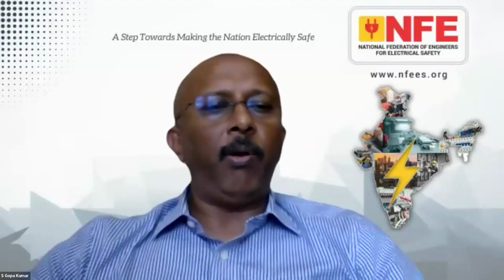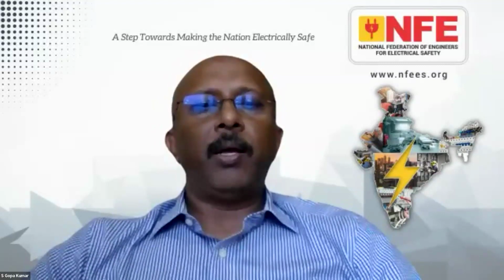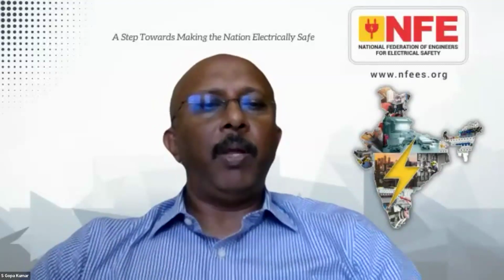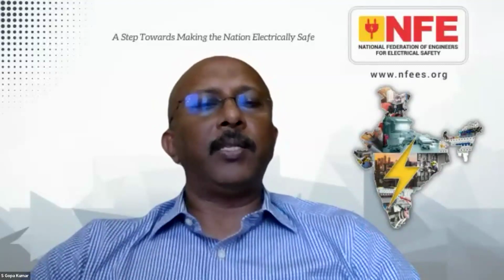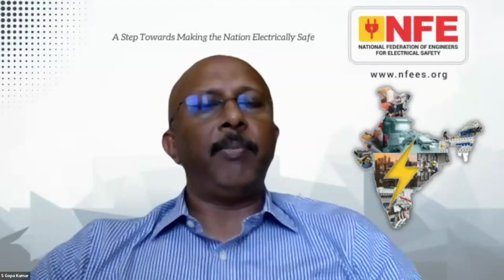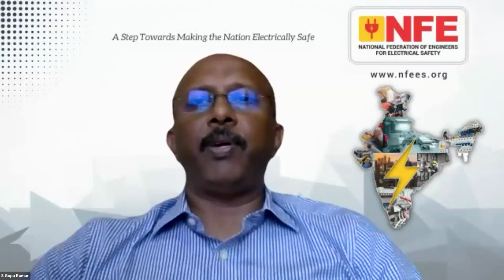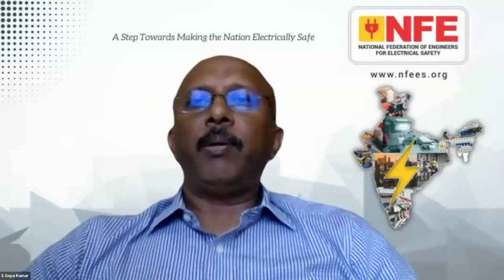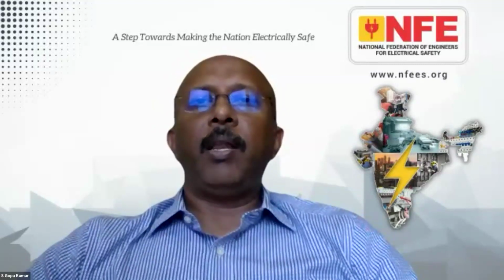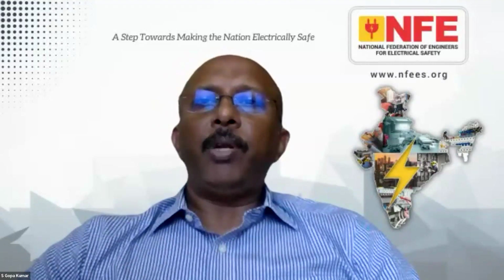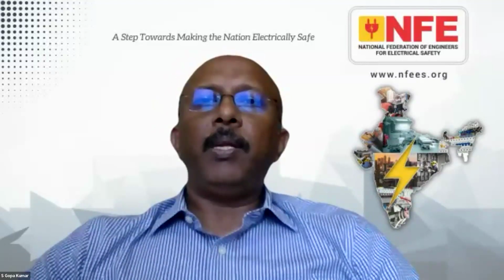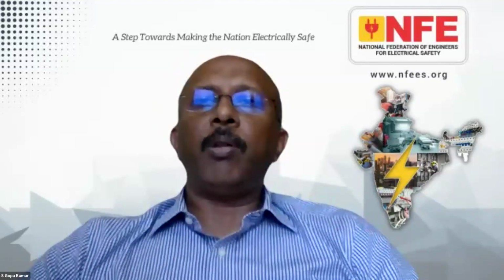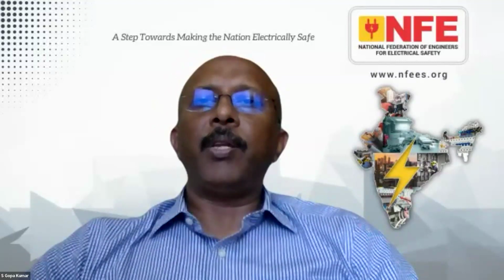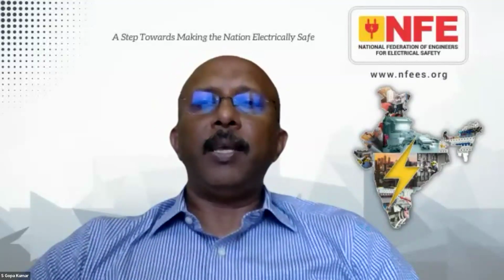If you are doing only fault loop impedance, the conclusion is probably that the efficiency of automatic disconnection is good. That's all. It doesn't mean that the installation is safe. So now, coming back to the question of Mr. Amritlal: when you are trying to test an installation, what will be the test voltage of the instrument, or the safety of the person likely to get a shock from the test equipment?